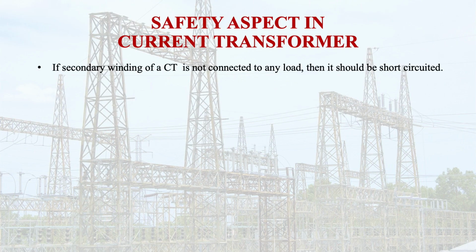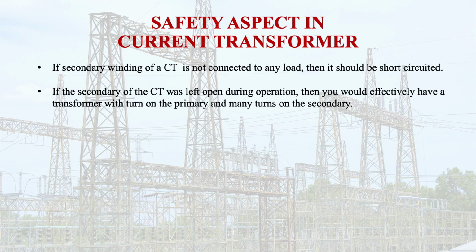Then what are the safety aspects in case of current transformers? If a current transformer secondary is not connected to any load, then it should be short circuited. That means we cannot keep it open. If the secondary of the current transformer is left open during operation, then you would effectively have a transformer with 1 turn on the primary and many turns on the secondary.